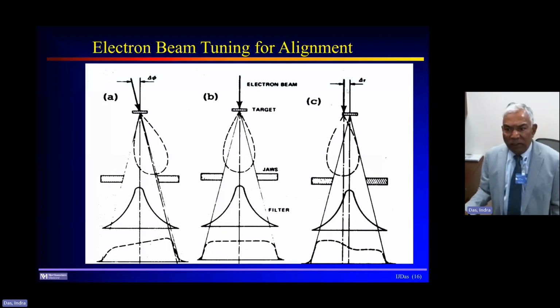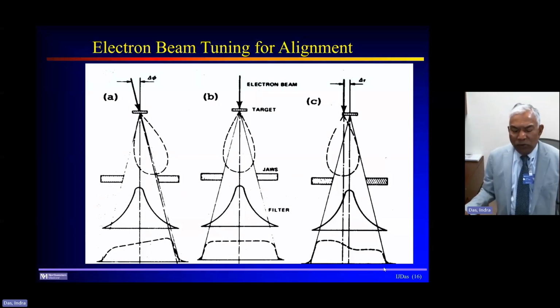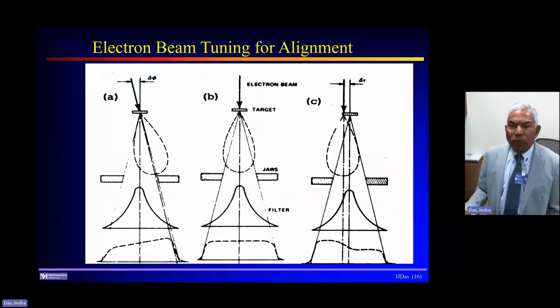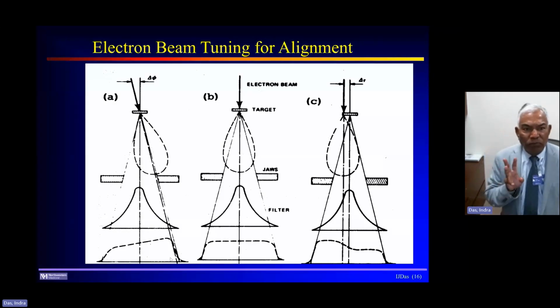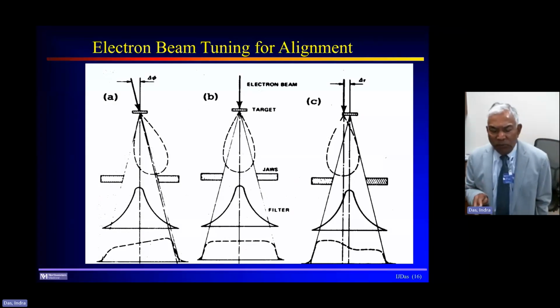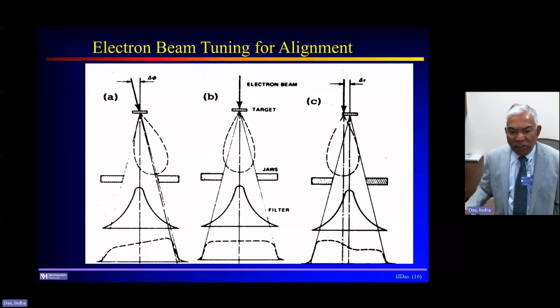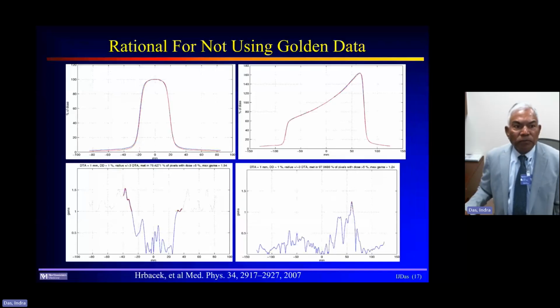But if it's not tilted, it's coming vertical, but it is off-centered, then also you will have this kind of skewness. So these are a problem. And so beam tuning at the site becomes critical. And this is a part of the acceptance testing, that you should make sure that your beam is perfectly all right, and also depth doses are within your tolerance. So those are something that you need to think about.